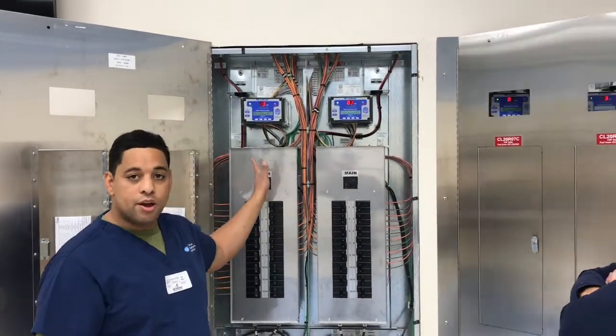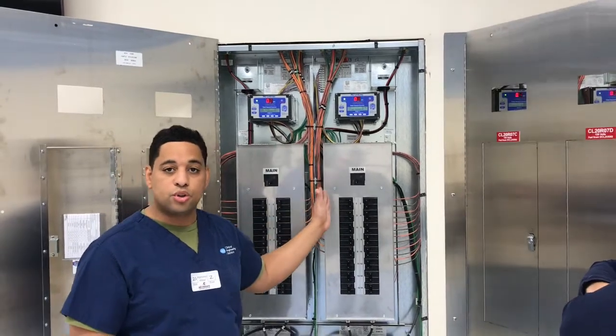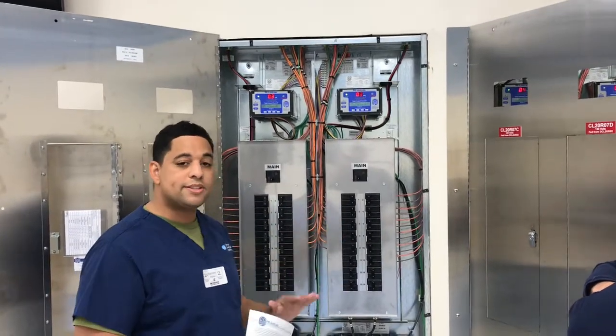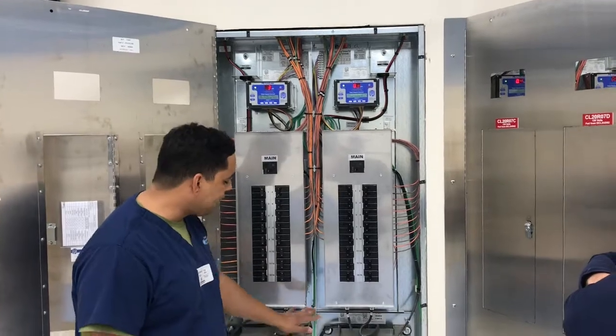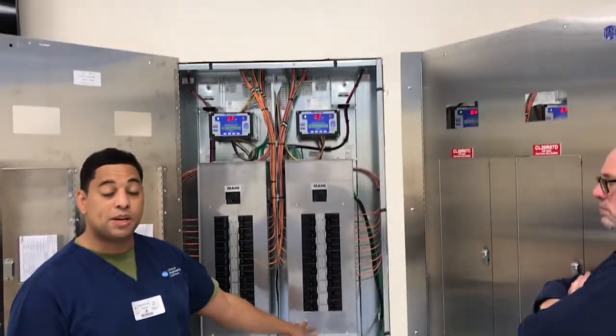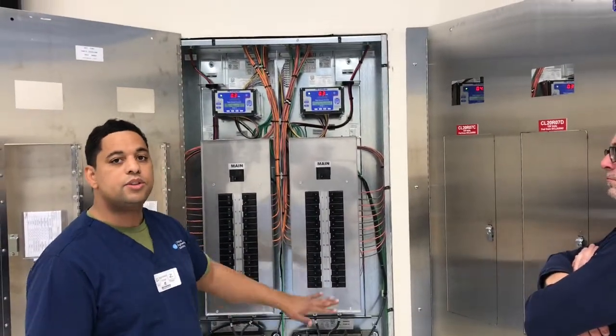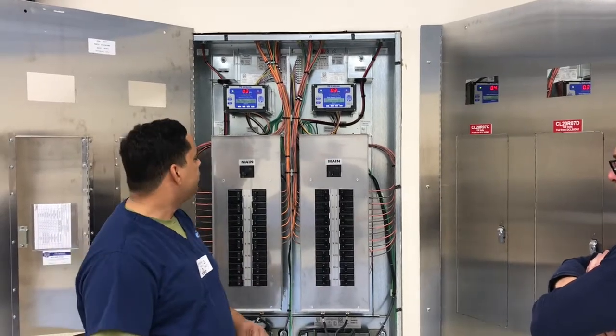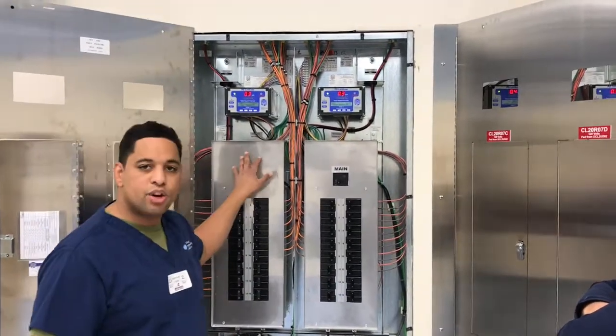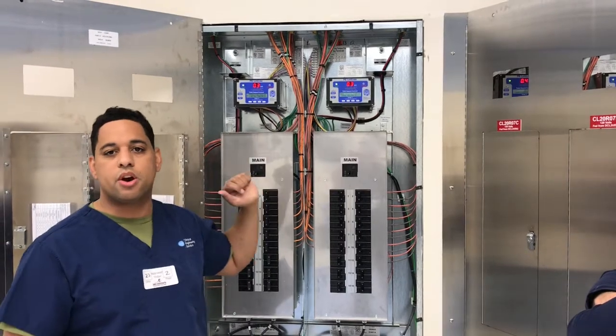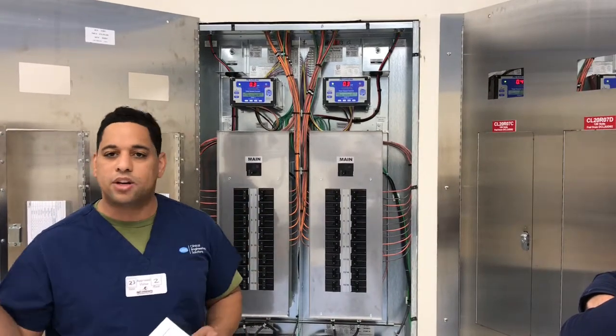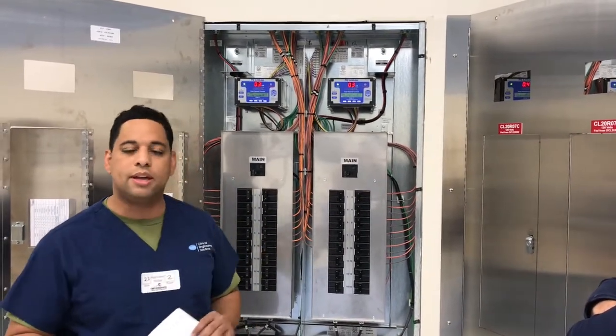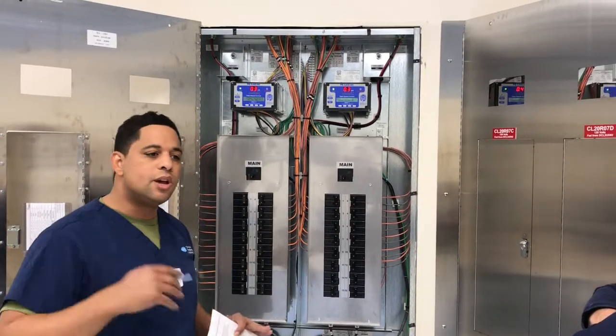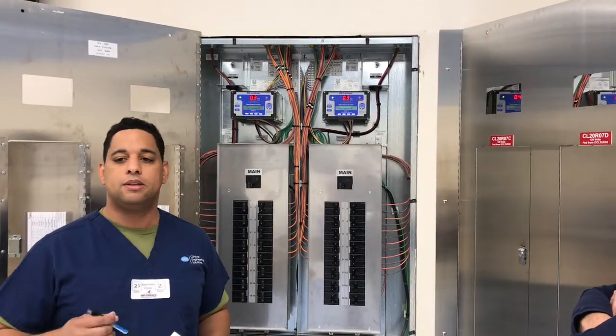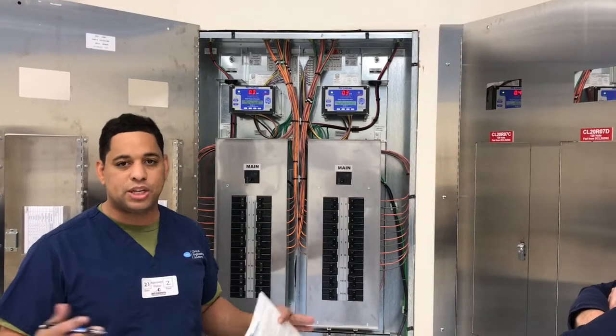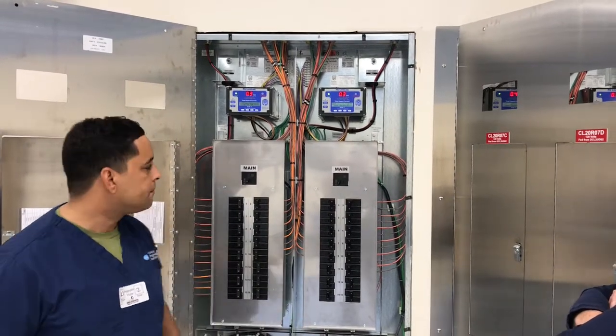Because normally the ground is connected to your neutral. In this case, it's separate, and so you have to have this panel specially built in order to do that. So it immediately grounds any kind of hazardous, dangerous current. It doesn't allow that current to travel through the room before grounding and possibly shocking someone, but most important, possibly shocking a patient during surgery.